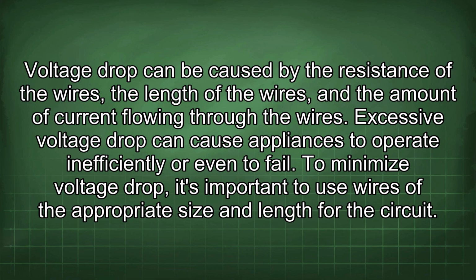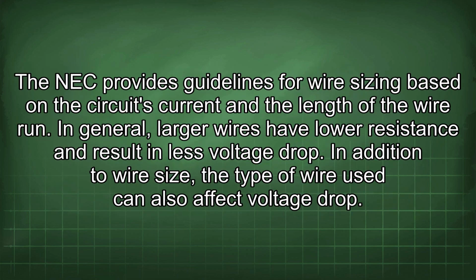To minimize voltage drop, it's important to use wires of the appropriate size and length for the circuit. The NEC provides guidelines for wire sizing based on the circuit's current and the length of the wire run. In general, larger wires have lower resistance and result in less voltage drop.